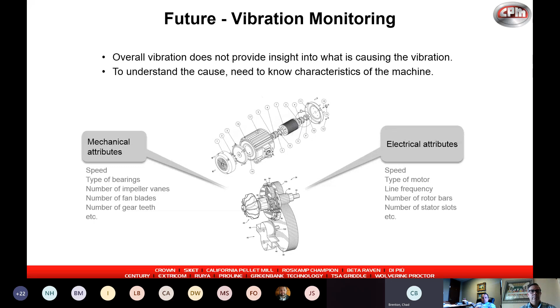We turn that one signal into various component signals. So if there are 8 balls in the bearing, we'll get a small spike in frequency 8 times per revolution. We can watch just that frequency and see if the acceleration is getting bigger or smaller. So when an alarm triggers, we can pinpoint more precisely - it's not just 'the machine,' it's a broken impeller, a bad bearing, or the motor out of alignment with the gearbox. It's a better way to quickly identify exactly what's causing increased vibration.